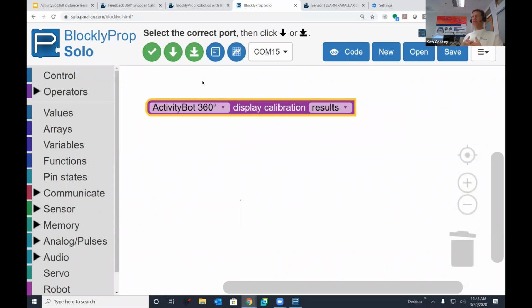Anybody else have trouble with calibration where it did download but then failed? Well, people might have their power switch in position 1 when they downloaded, but not moved it to 2. Claire, when you ran it, did you put it in position 2? I did. It said it calibrated great. I double pushed my yellow pins down in case maybe they weren't. The yellow button just flashed, so I'm turning it off, correct? Okay. Then I'm unplugging it. Then I'm moving to my kitchen floor, and I'm putting it on 2.